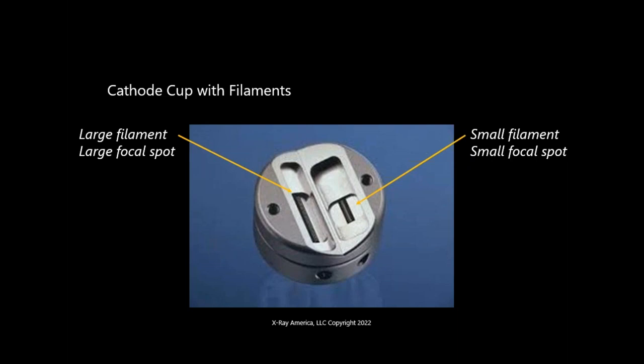Everything has to stay in place to make that tube work. I mean, the architecture, the geometry has to stay. You can't have a cathode bending, you can't have your anode moving, because of the tremendous amount of force. And by the way, no one's gotten to 0.2 seconds. A few people have claimed to, but no one's gotten to 0.2 yet. 0.25 is about the fastest spinning rotation. If you have a system that'll do 0.25, you don't want to use it unless you really need it. You want to use a slower rotation because you're really at the edge of physics when you get to that. Everything else is fine. Better have that thing shimmed properly. Yeah, it needs to be balanced. I mean, there's a ton that goes into it.